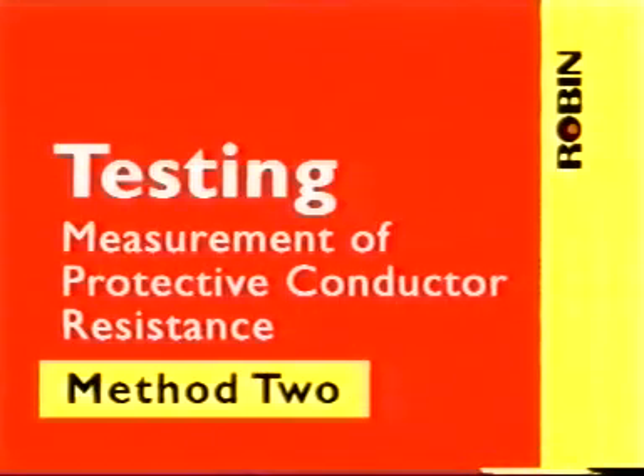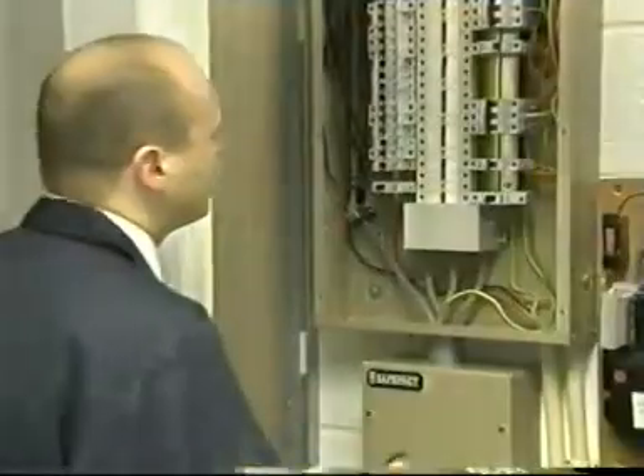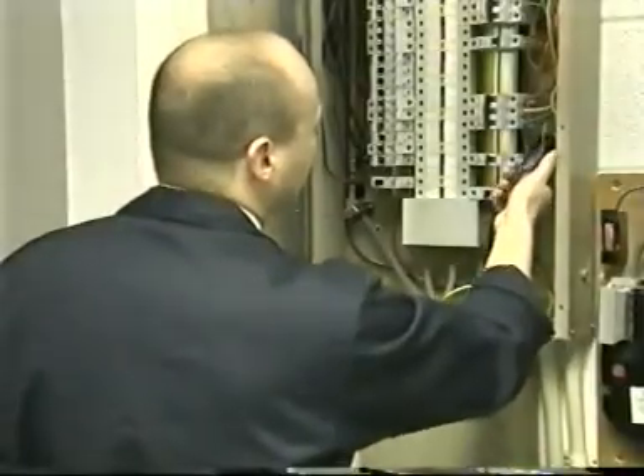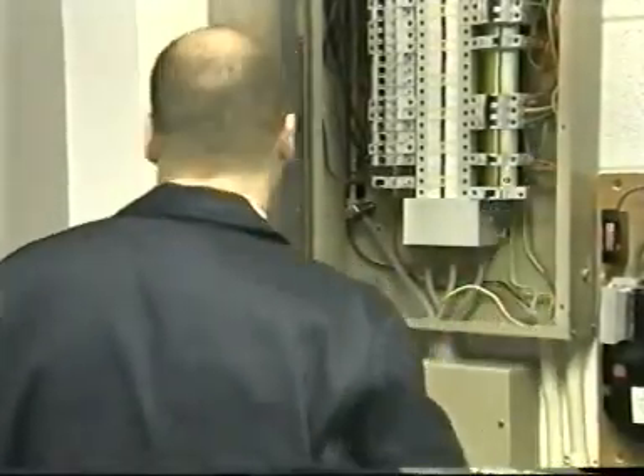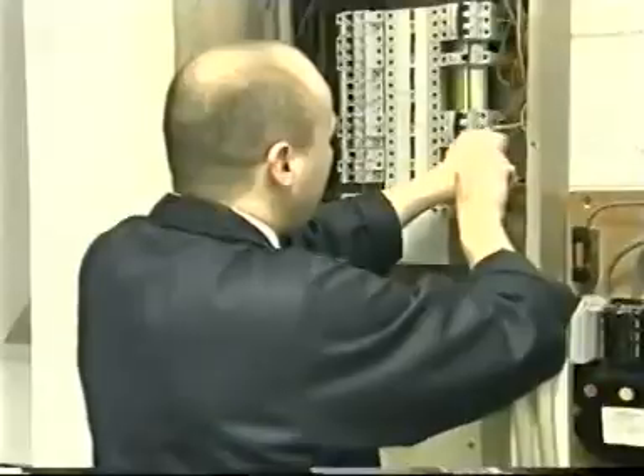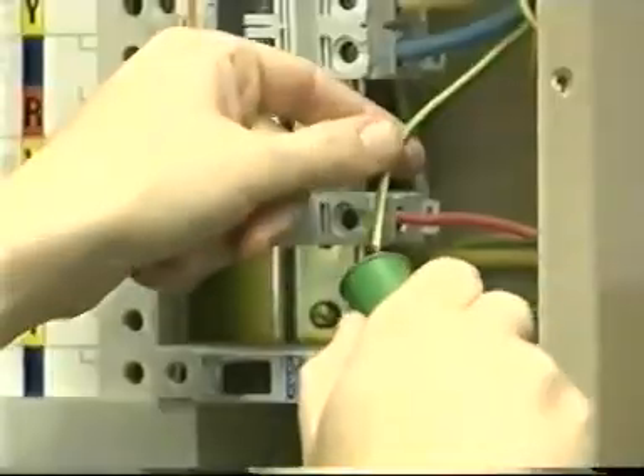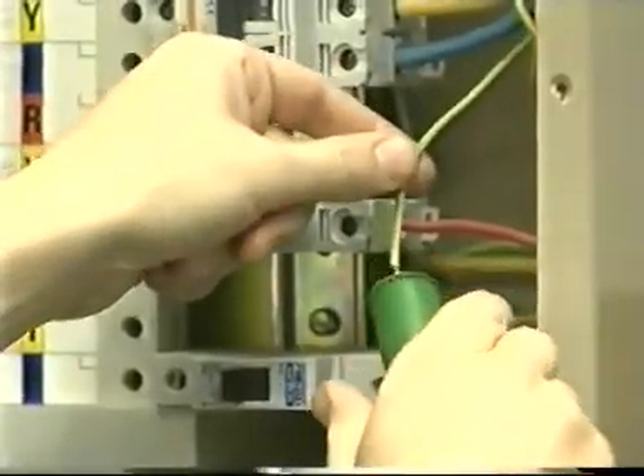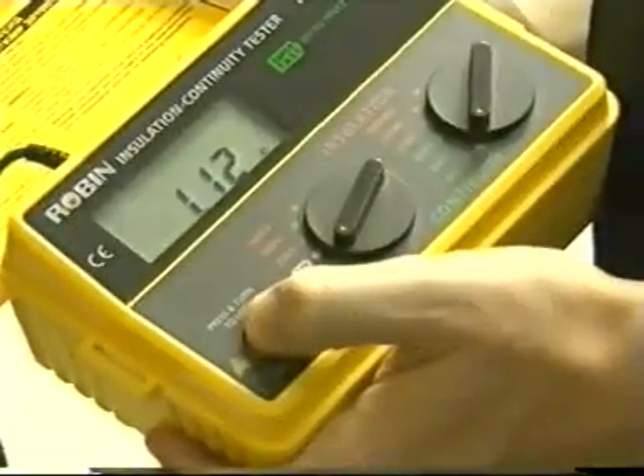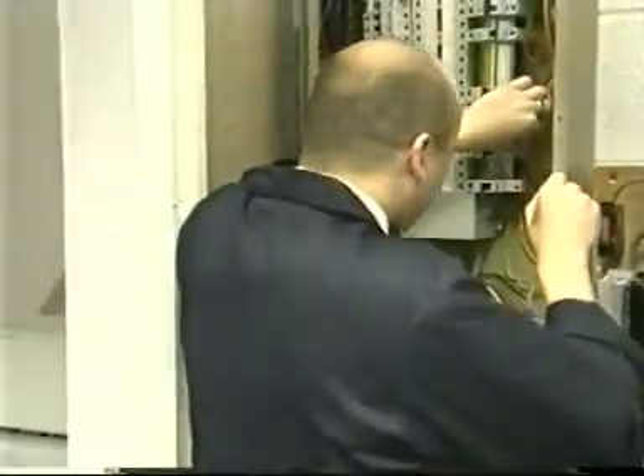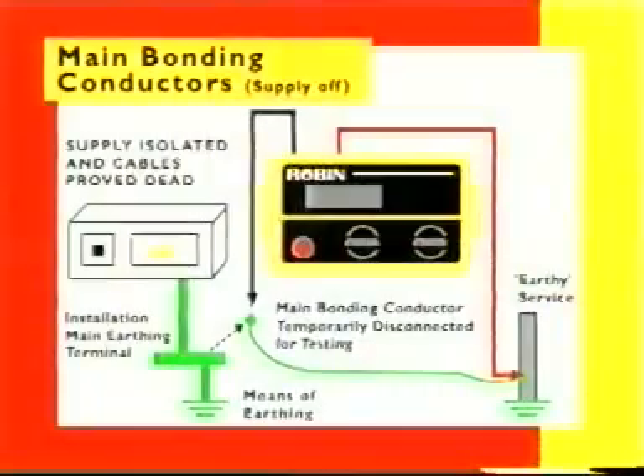Method 2 uses a wander lead connected between the consumer's main earthing terminal and continuity tester and can be used for verifying the protective conductor continuity of a radial circuit. With the short lead connected to the instrument, contact is made to every accessible exposed conductive part in the installation. The conductor must be soundly reconnected before reinstating the supply. It's also commonly used for verifying continuity of main equipotential bonding conductors.